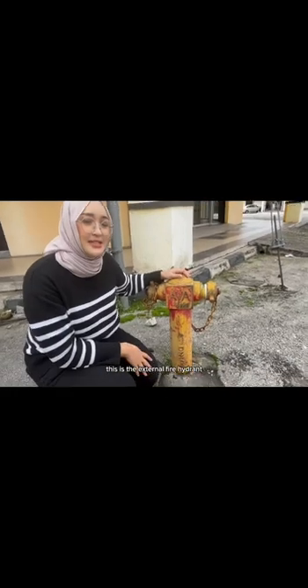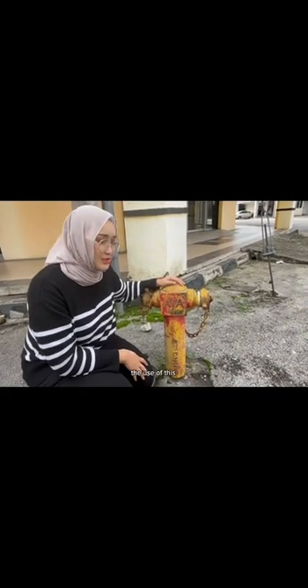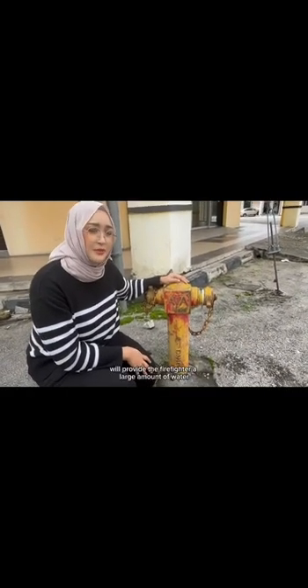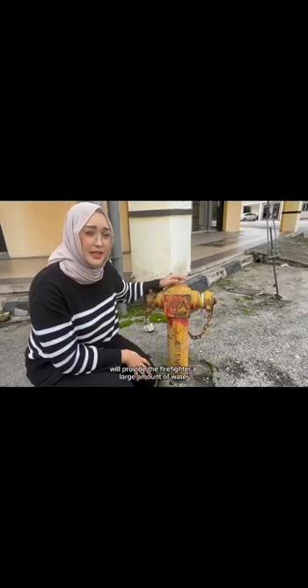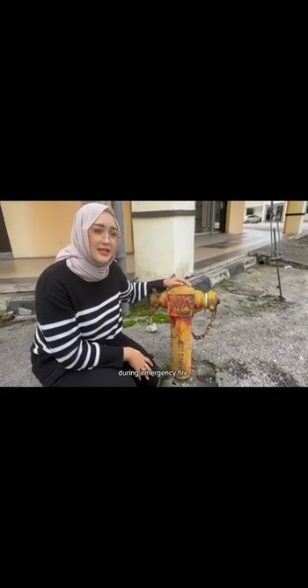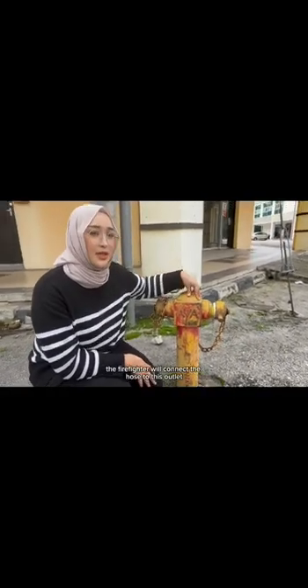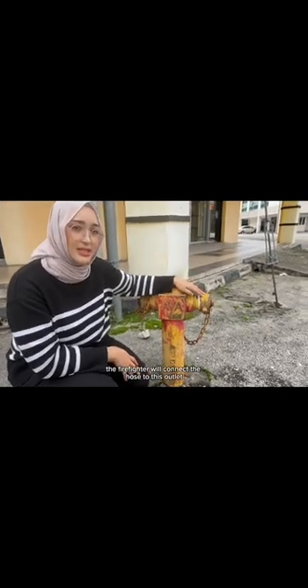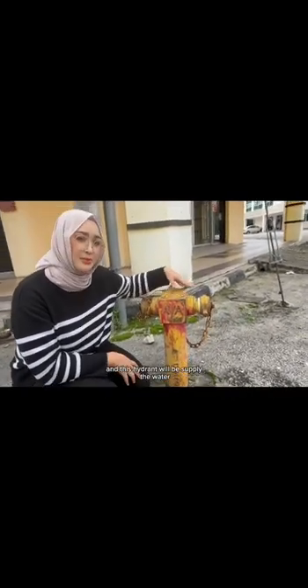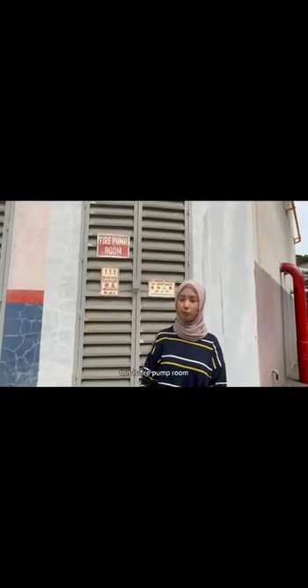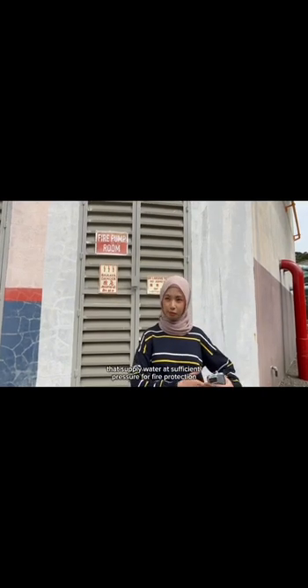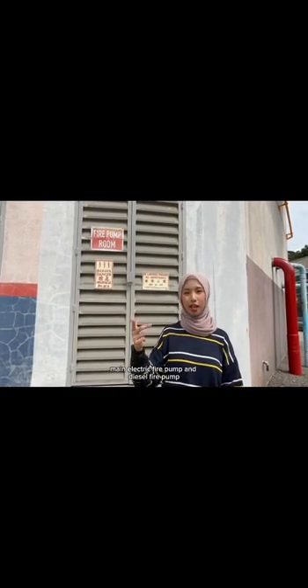Okay, this is the external fire hydrant. The use of this is to provide the firefighter a large amount of water during an emergency fire. The firefighter will connect the hose to this outlet, and this hydrant will be supplied with water. This is the fire pump room that supplies water at sufficient pressure for fire protection. It consists of a jockey pump, main electric fire pump and diesel fire pump.